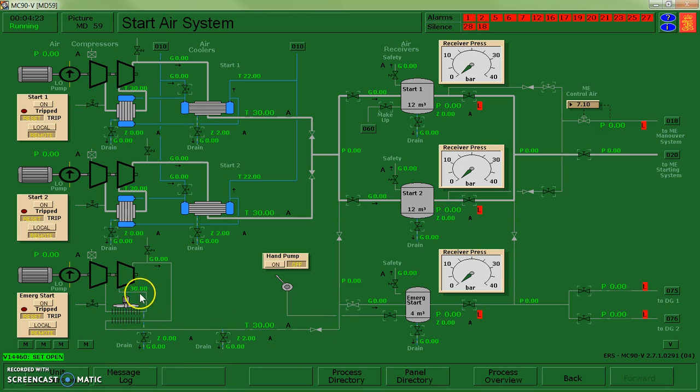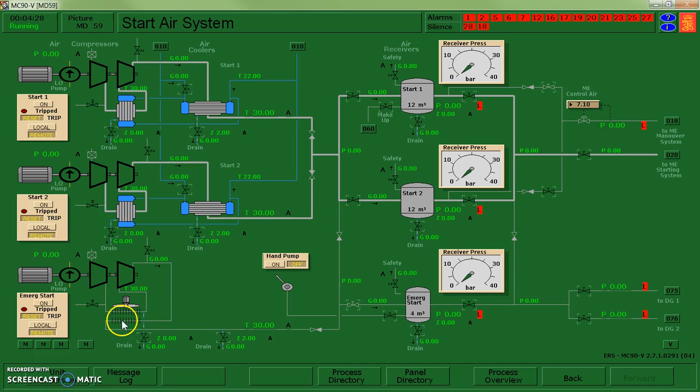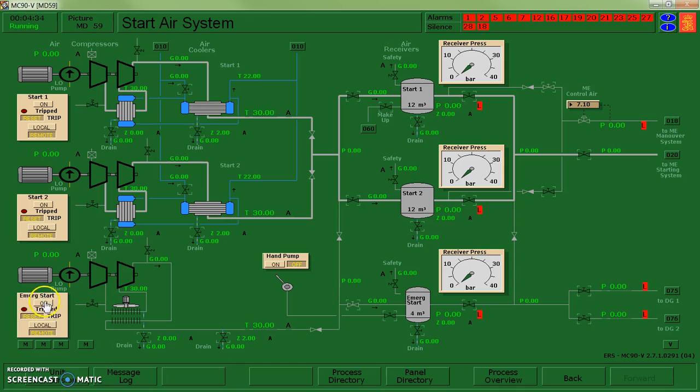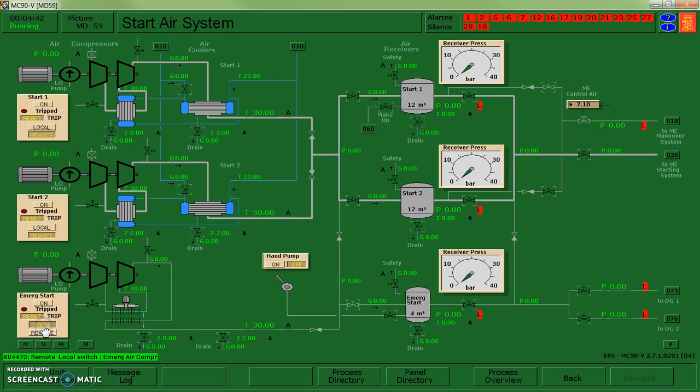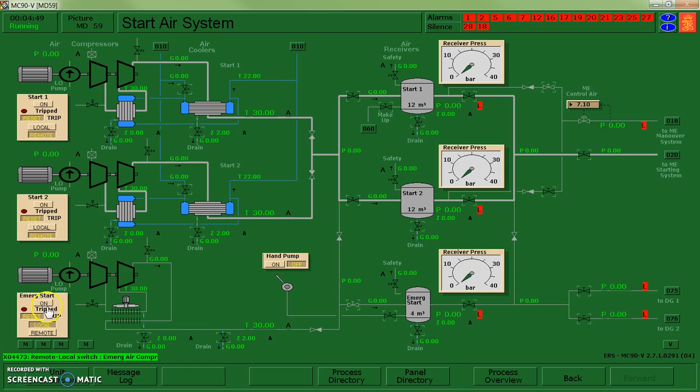Follows it back. Looks like I don't need any cooling water system in this case. It's a fan cooled and air cooled radiator of some type. So I don't need cooling water. Looks like I'm ready to start. You can see before I start I have this set to remote. What I want to do is switch it over to local. And what that's doing is it's transferring the duty of starting or stopping this device to the local control panel. So the push button right on it, this on button, now is active.